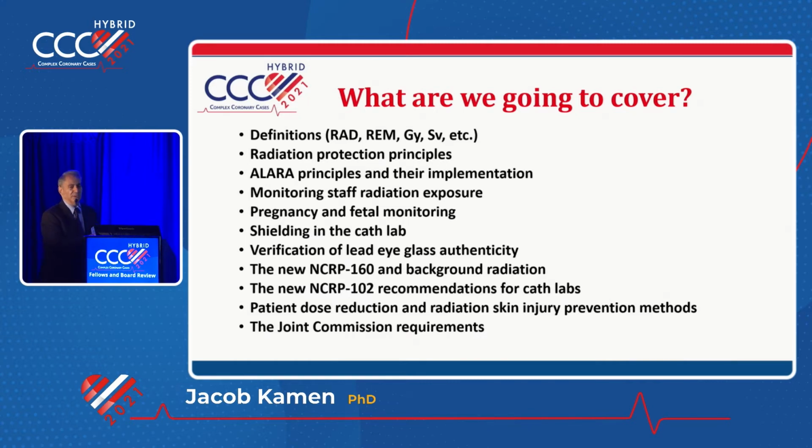You have to be careful because some of the eyeglasses they sell in the market is not real, and you have to test it to make sure it's really lead in it. Mention a little bit about NCRP 160, NCRP 102 about recommendation for Cath lab, and patient dose reduction. That's a very, very important topic because lately regulations are changing, especially about patient skin dose. The Joint Commission requirement is a new requirement that I will try to cover.